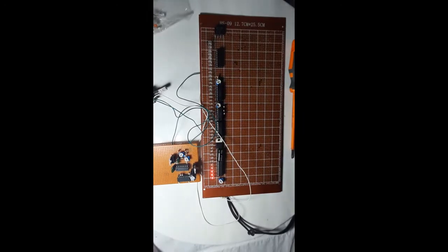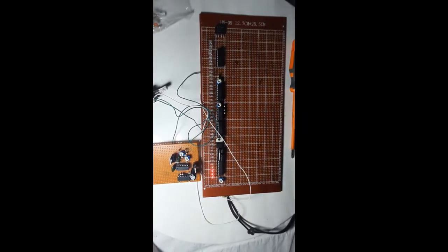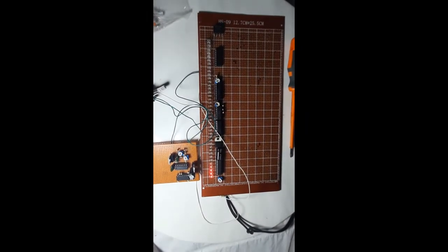Now we have to eliminate this error. We have discussed the error correction with the graph and all. So you have to draw a graph to correct the errors, right? I will show you the graphs which I have drawn to eliminate the errors of this. Now this is a graph which I drew about the transducer. You can see initially there's an error, but there's no linearization error. It is very linear. But there's a zero error. If there were no zero error, this line must cross at the 0, 0 point.